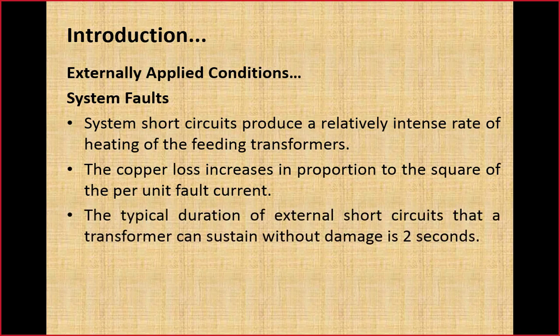So remember, the transformer design includes that a transformer should be capable of withstanding an external fault current for 2 seconds, and 2 seconds is sufficient time for any primary protection or backup protection to operate and clear the fault. But if the fault is not cleared even after 2 seconds, then the transformer protection should come into action and remove the transformer from the system. Otherwise, the transformer may get damaged.